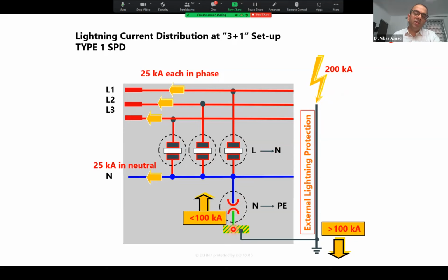You see this arrestor, the current is coming from this side, earth towards the line. So it is having the full current, 100 kiloampere, which is left out from the earth, right? So the arrestor which is connected between neutral to earth will have to be designed for 100 kiloampere. And after that only it is getting divided into 4 lines. One is the direct line to the neutral going to the center of the transformer. The other is through these 3 SPDs going from the lines and then the phases of the transformer, then to the center and then to the earth.